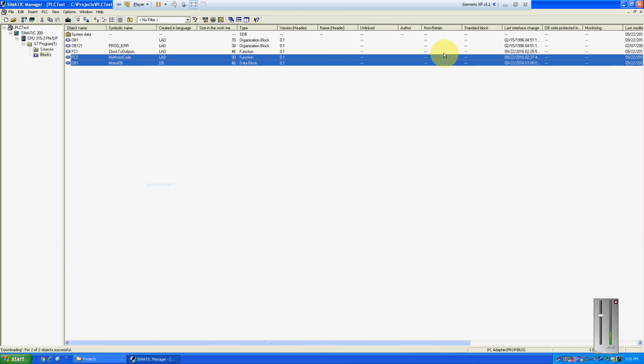Why did you delete? So I deleted OB1 because it will make it very clear if it tried to access the invalid memory. So if OB1 was in there, and say for 1 or 2 cycles it tried to access memory that wasn't there, it wouldn't stop the PLC, it would give an error, but as soon as the memory was there, it would work fine.